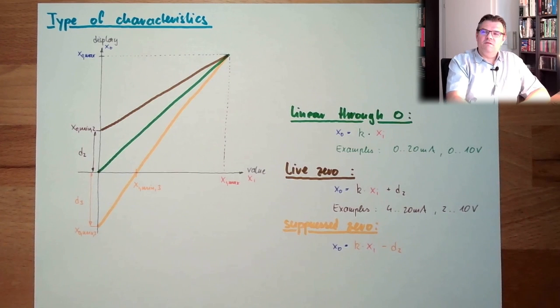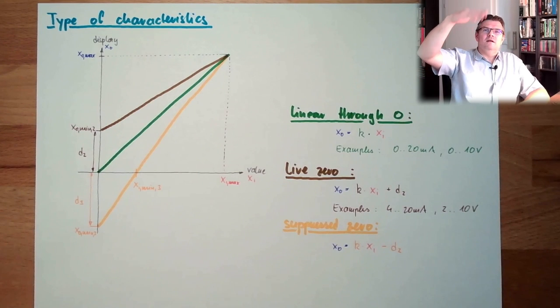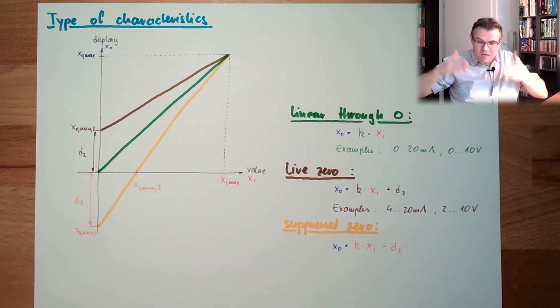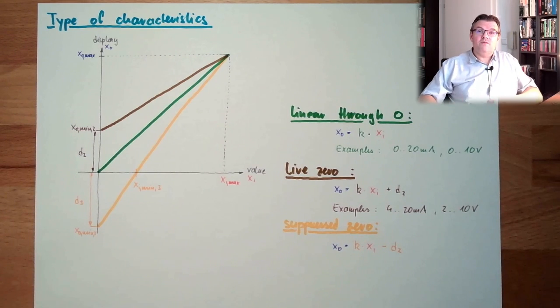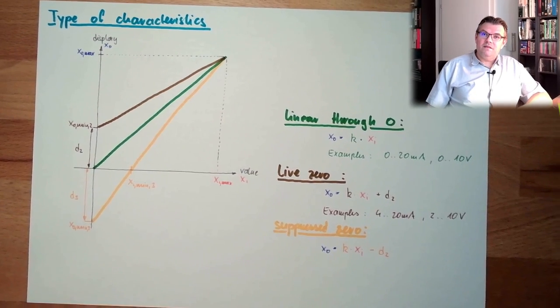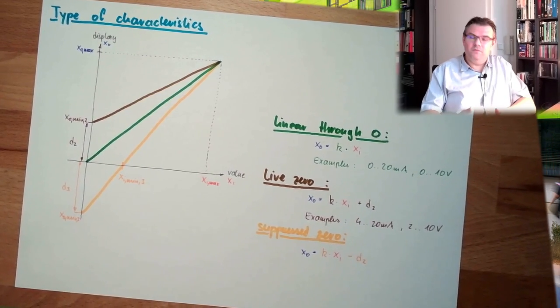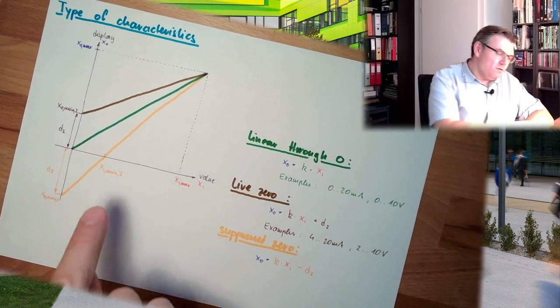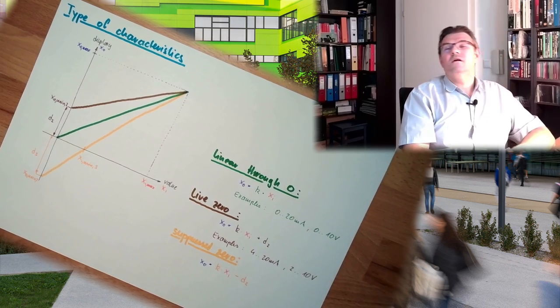Or, for instance, a level measurement at some lake in the mountains. You don't start at sea level. It's in the mountains. If it is fully empty, the ground will be at, I don't know, 2,300 meter sea level. There is no sense to start from zero. I start at 2,300 because then the lake is already empty. And at 2,380, it's 80 meters filled. So, you know what I mean? Often you have this type of line without even noticing. Type of characteristics.